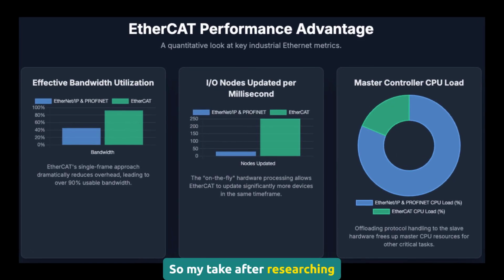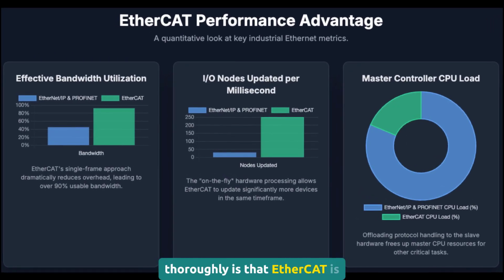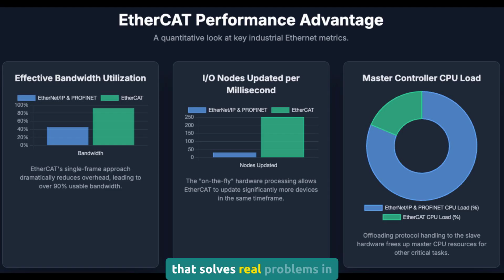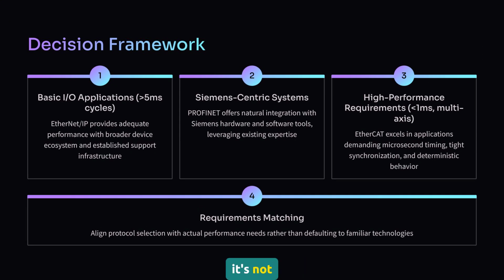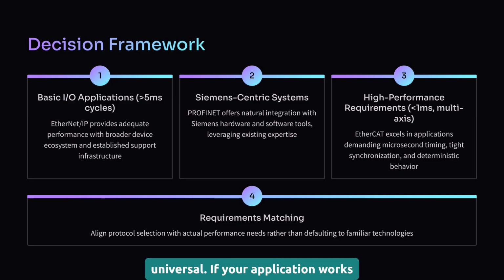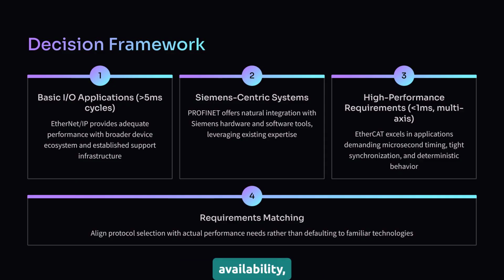So my take after researching this protocol thoroughly is that EtherCAT is impressive engineering that solves real problems in high-performance applications. The processing-on-the-fly architecture eliminates bottlenecks I've dealt with for years in standard Ethernet installations. But like any tool, it's not universal. If your application works fine with 5 to 10 millisecond cycle times and you need broad device availability, Ethernet IP is still a solid choice. If you're in a Siemens world, PROFINET makes sense. EtherCAT shines when you absolutely need microsecond level timing and tight synchronization.